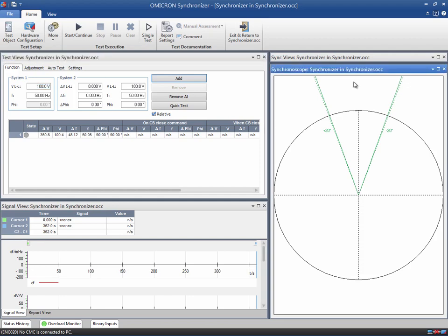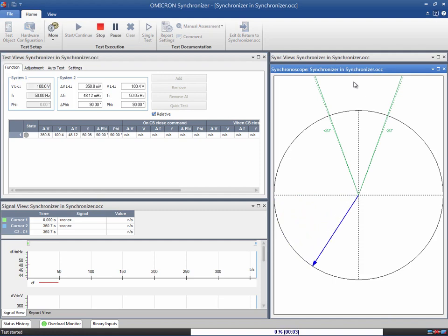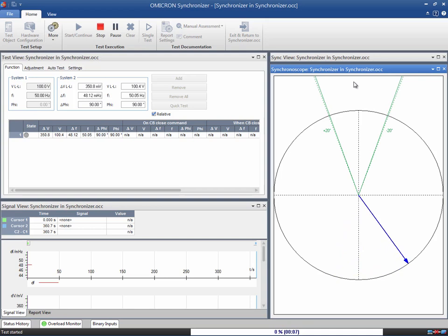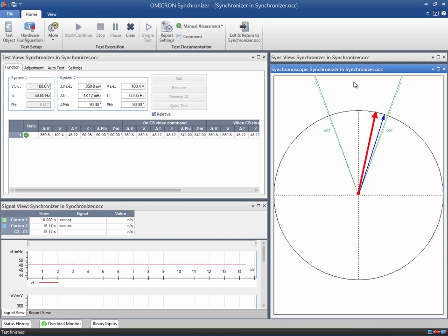When the test is started, the blue arrow rotates in order to show the phase difference being measured between the two systems. The higher the frequency difference between the two systems, the higher the rate of change will be for the phase difference. The blue arrow stops when the relay issues the Circuit Breaker Close command. A red arrow appears after the closing time to show when the Circuit Breaker is actually closed.